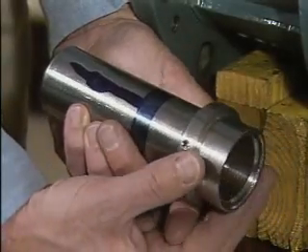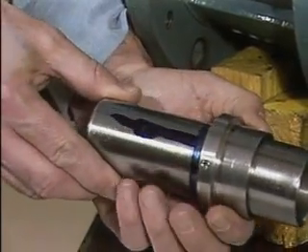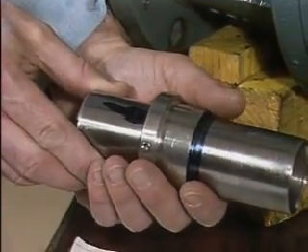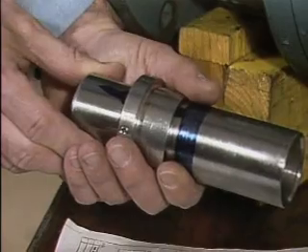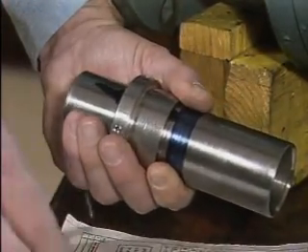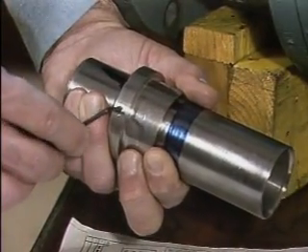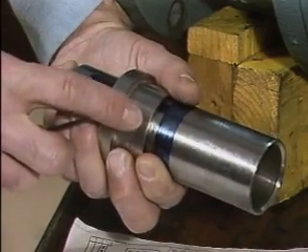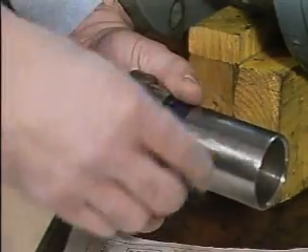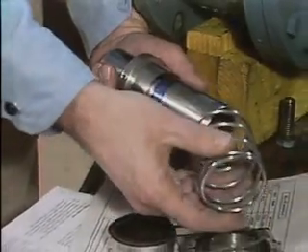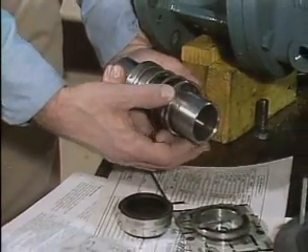The first step is to mount the collar. The collar is slid onto the sleeve so that the end of the collar that's opposite the seal face is positioned at the line that was scribed according to the location dimension. Next, the set screws are partially tightened to hold the collar in place. The spring is positioned on the sleeve.